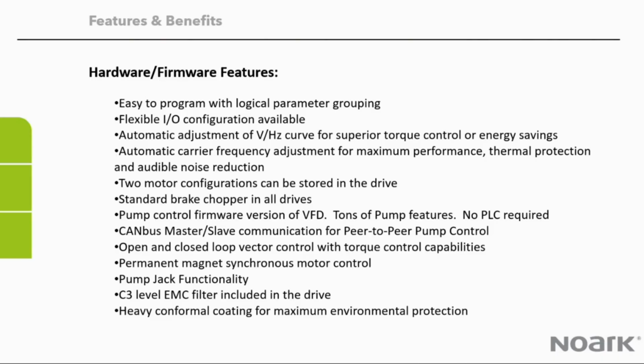A C3 level EMC filter is included in the drive because the drive, before being brought here to North America, has been sold for a number of years in Europe and in other parts of the world where EMC noise levels are mandatory to be below a certain level. So we have the capability in the drive to have that component in there, and it will be in there all the time, actually. We're not going to take it out even if you don't need it. It's so much embedded into the drive. The other thing is we put a heavy conformal coating on the printed circuit boards to help with caustic or humid or moisture-ridden environments. That helps seal the board and the components so that they don't run into any kind of condensation issues.